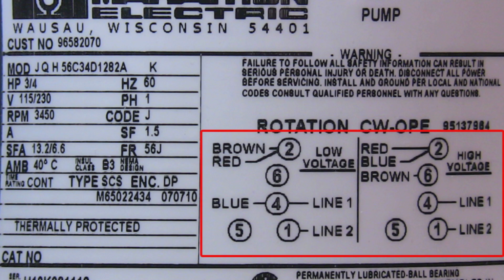For a multi-voltage motor, the wiring diagram is split into 2 sections. The left section, labeled as low, indicates wire placement on the terminals when the lower voltage is applied, in this case 120 volts. The right section, labeled as high, is for 230 volt applications. The circles indicate terminal numbers found under the electrical access cover. The information found to the left of these circles indicates wires within the motor, while the information to the right indicates wires from the machine.